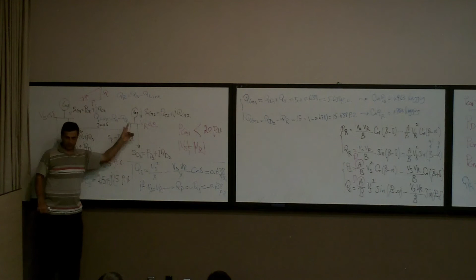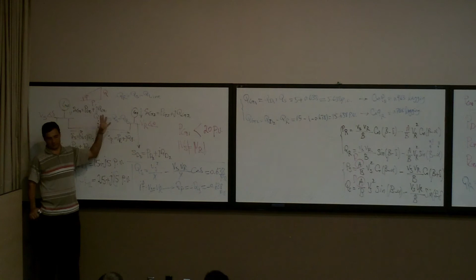But I want to keep the voltage fixed. If I want to compensate in general, if I want to compensate the voltage drop, they call it voltage boosting. I want to boost my voltage, I need to inject reactive power. Look at here, the generator number 2 is injecting how much? 15.638 reactive power. So this one is injecting reactive power here to compensate this voltage.